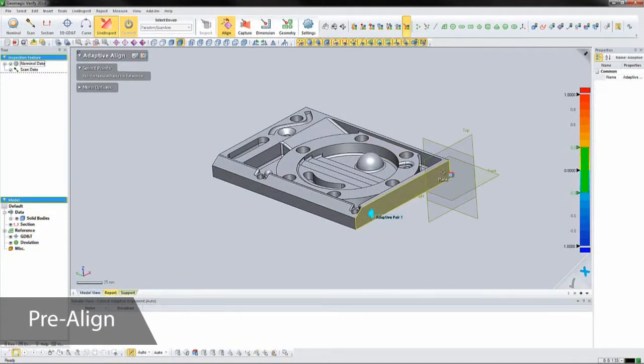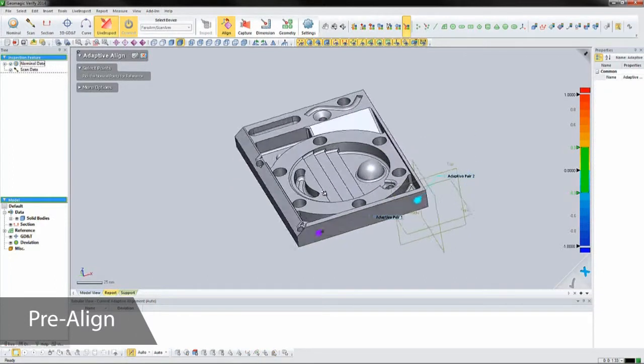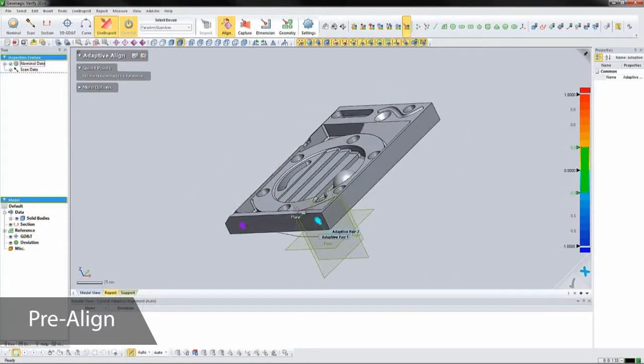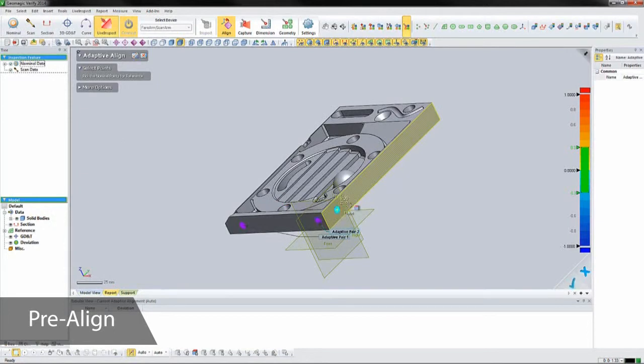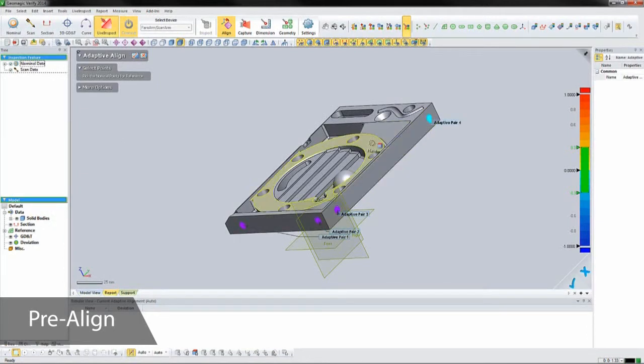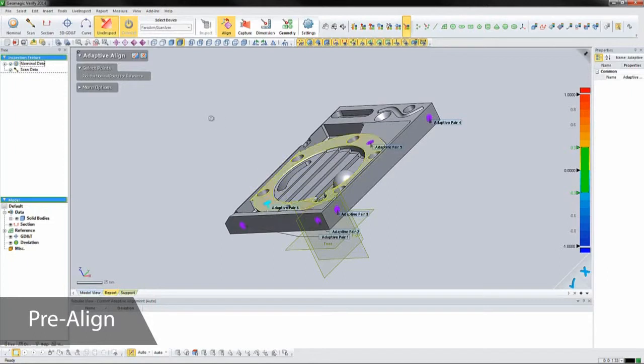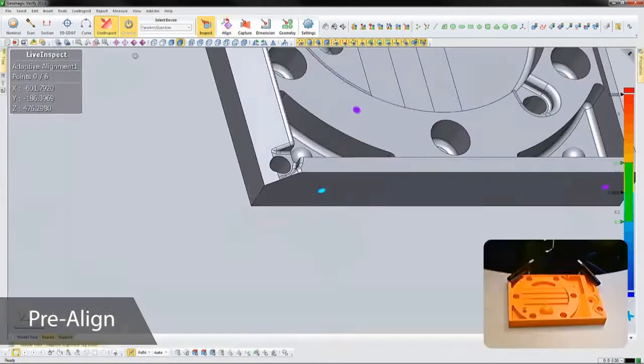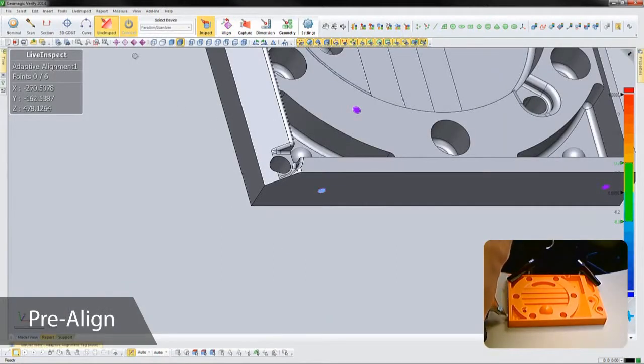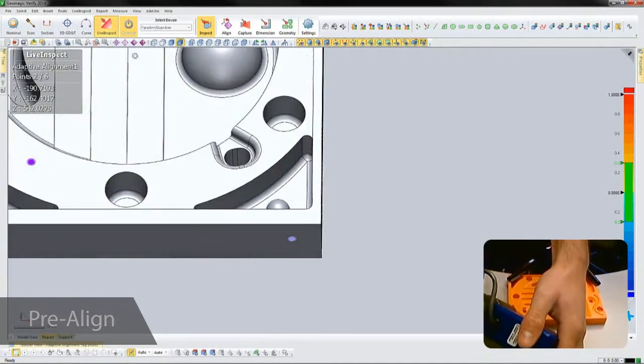An interactive alignment will sync the orientation of the physical part to that of the nominal file. After we define the alignment points to probe on the model, Verify will walk us through probing them on the physical part, then let us validate the alignment and reiterate it if the deviation is too great.